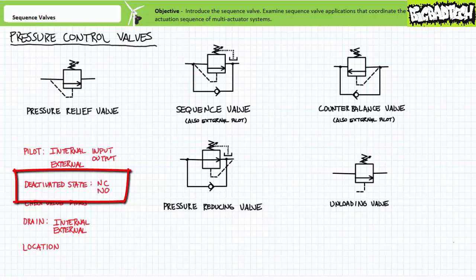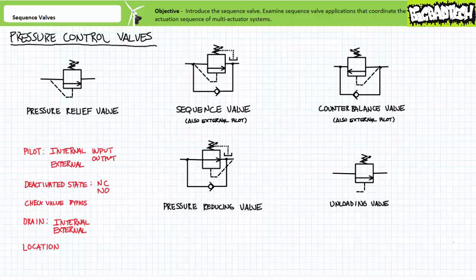Deactivated state: all pressure control valves have a deactivated state. When pressure in the pilot line exceeds the adjustable set value, the valve actuates into its opposite state. Most of these valves are normally closed and open when pressure exceeds the set value, operating just like an ordinary pressure relief valve. The exception is the pressure reducing valve, which is normally open, and when pressure exceeds the set value, the valve closes. That's a dead giveaway.